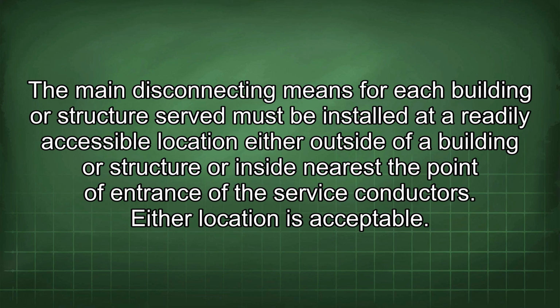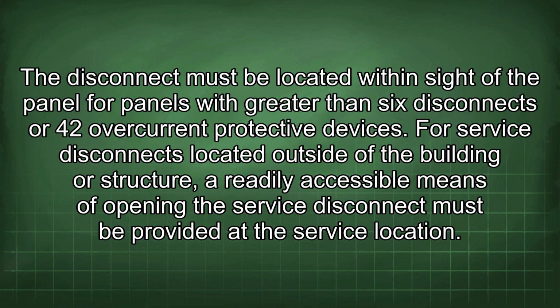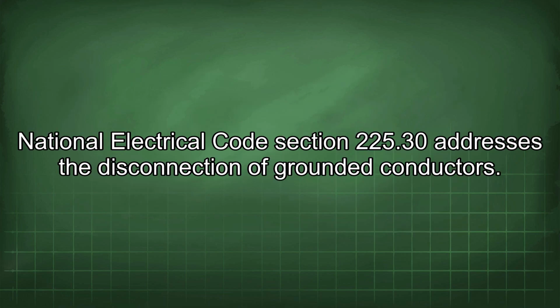Either location is acceptable. The disconnect must be located within sight of the panel for panels with greater than 6 disconnects or 42 overcurrent protective devices. For service disconnects located outside of the building or structure, a readily accessible means of opening the service disconnect must be provided at the service location. National Electrical Code Section 225.30 addresses the disconnection of grounded conductors.